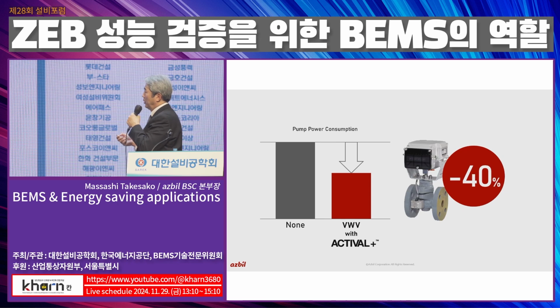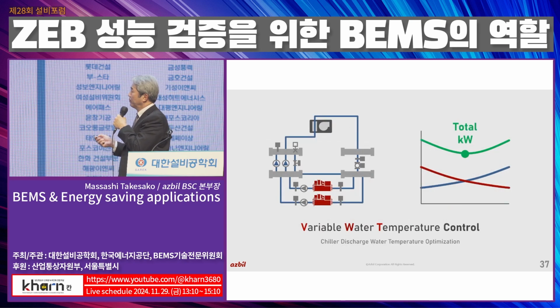So this is the result. This is just an example, 40% pump power consumption can be saved from those applications. Also, this is the next one. It's variable water temperature, which is the chiller leaving water temperature. I don't know whether in Japan also, in Southeast Asian countries also, maybe more than 99%, the chiller leaving water temperature is always constant, regardless of load fluctuation. Even the season is the same. Even in winter, the chiller leaving water temperature is always 7 degrees or 8 degrees.